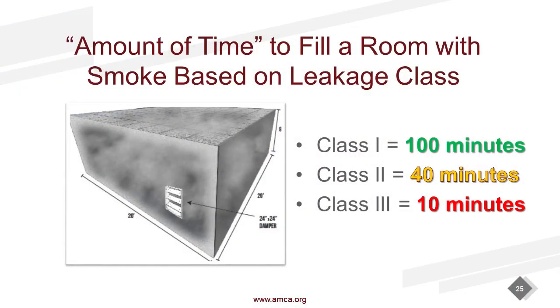International Building Code, again, requires minimum Class 2. If it was a Class 2 damper, hypothetically, that room would fill up with smoke in 40 minutes. Commercial building, couple floors, mid-rise, that's enough for healthy, capable people to stand up and walk out and evacuate in a safe and orderly manner.